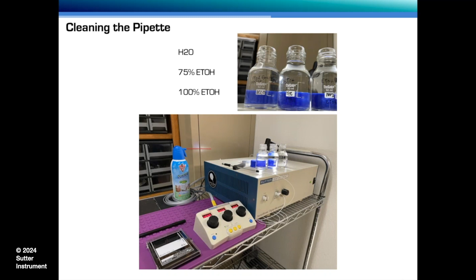Yes, you need to take the entire system, not the entire system apart, but you need to take the top pedestal piece off. You need to remove the retaining ring and the beveling plate, and you need to clean the bottom of the beveling plate with 75% ethanol or degreaser. Do not get that oil or the 75% ethanol or the degreaser on the top of the plate, because it might ruin the surface or wash off the diamond granules. So I'm washing off the bottom of the beveling plate, and then you're going to clean the top of the plate with pure water, shown here. And then you're cleaning the optical flat too. Don't forget that, clean that off also. And that would be with ethanol and or degreaser.